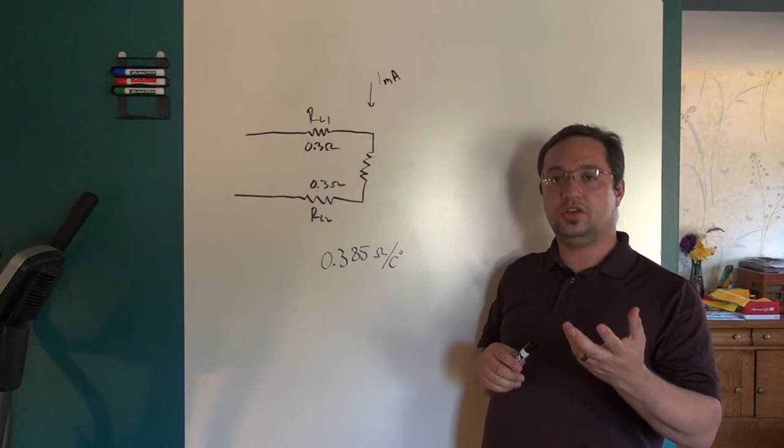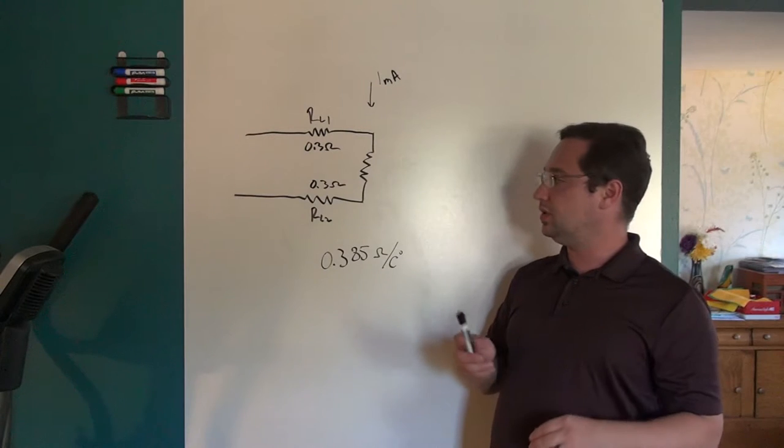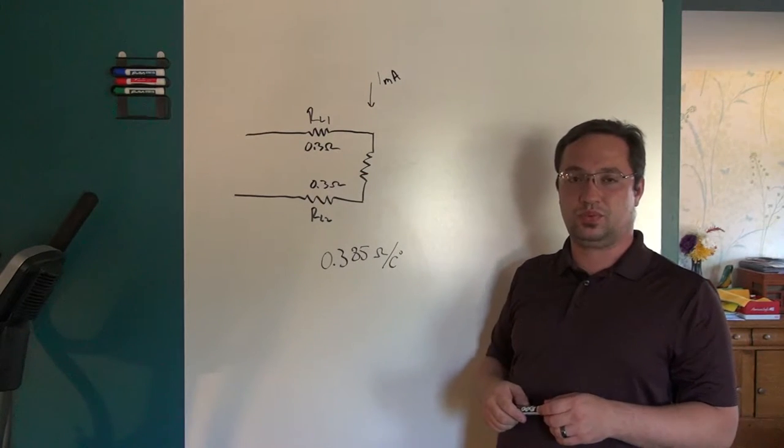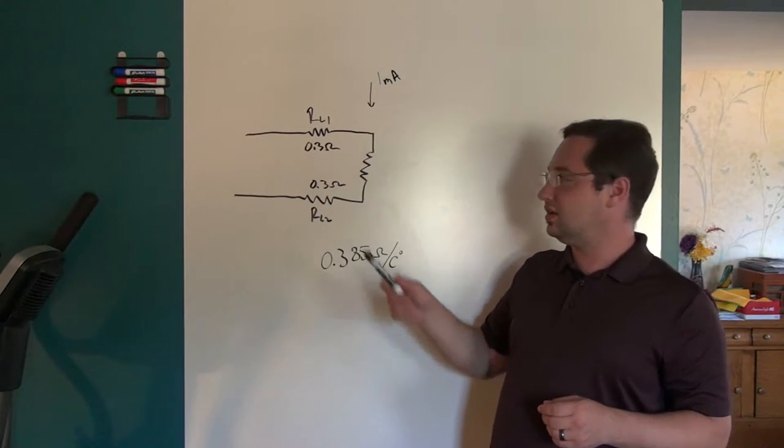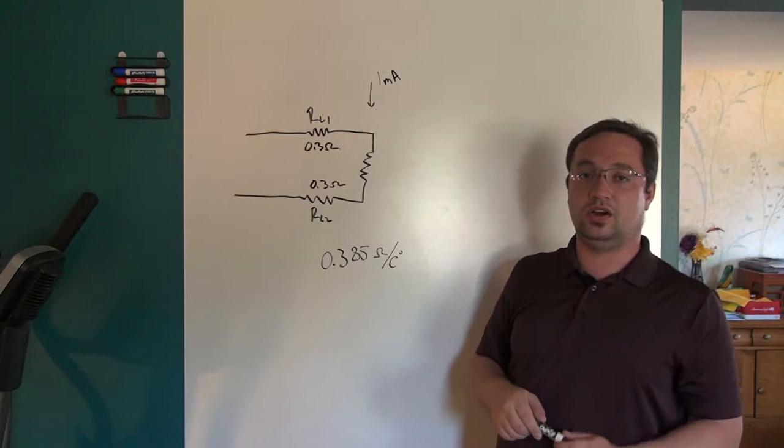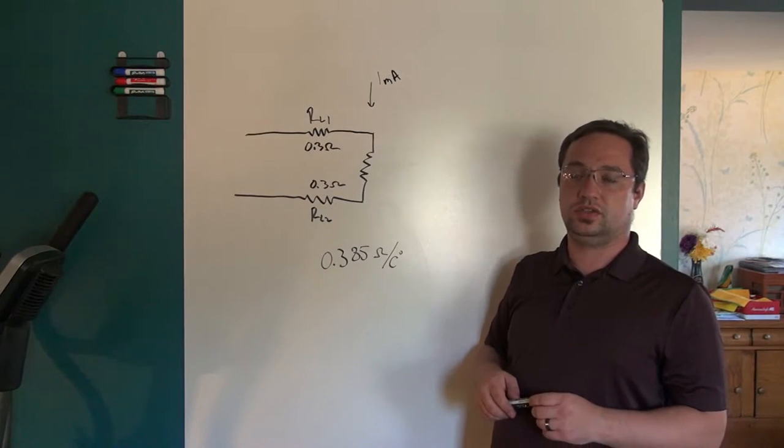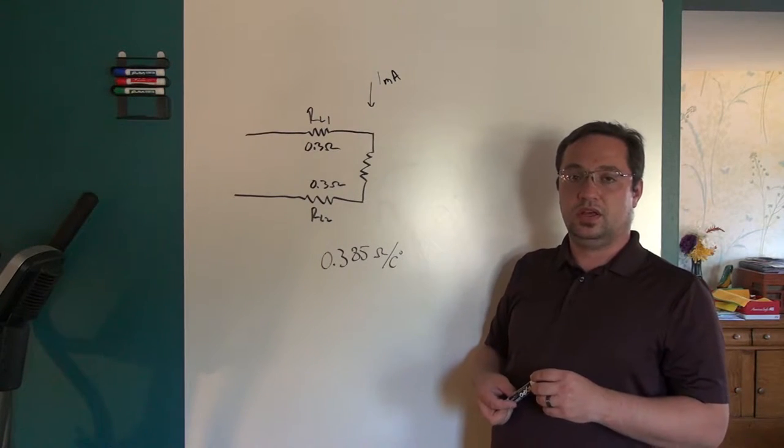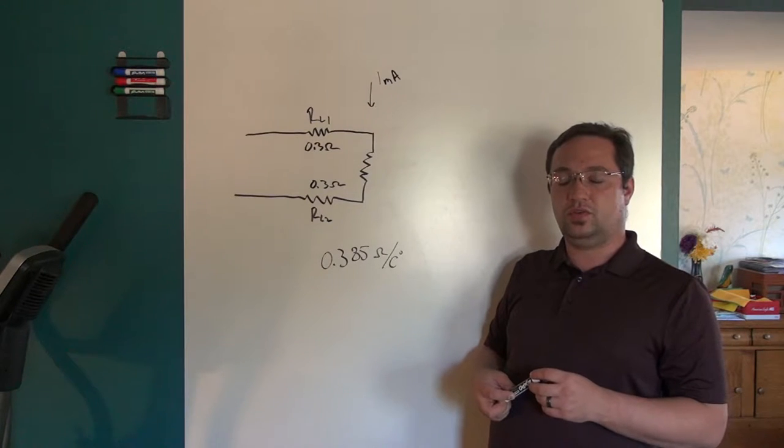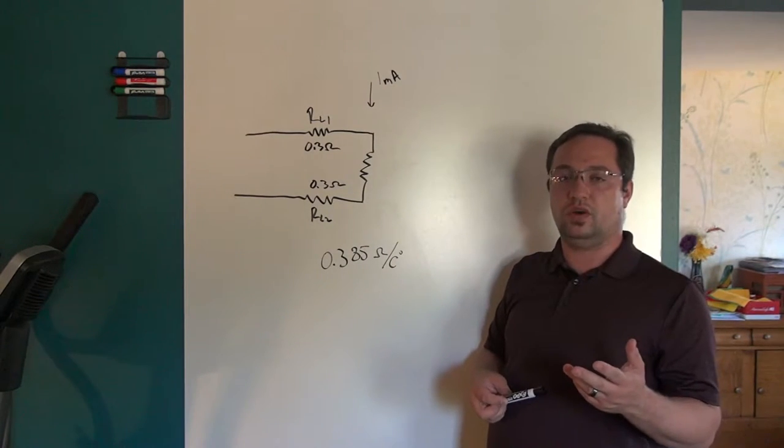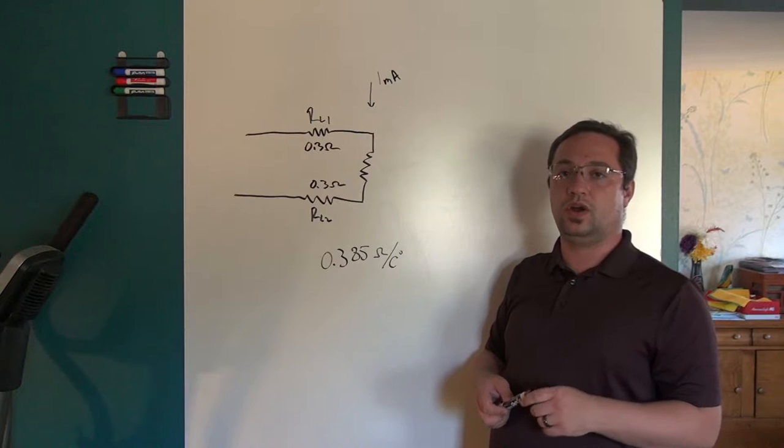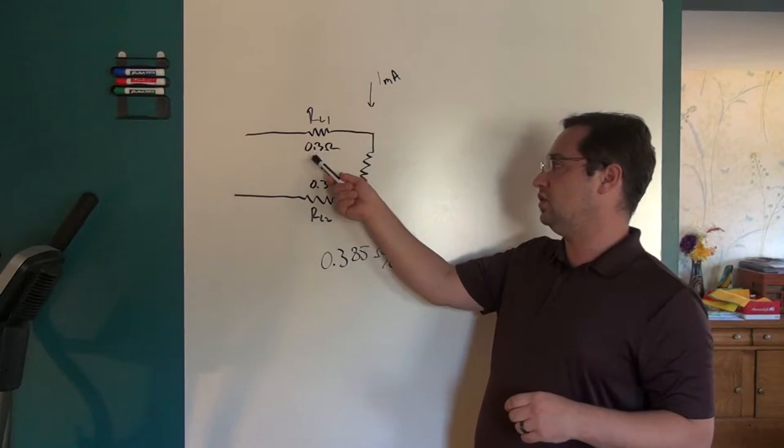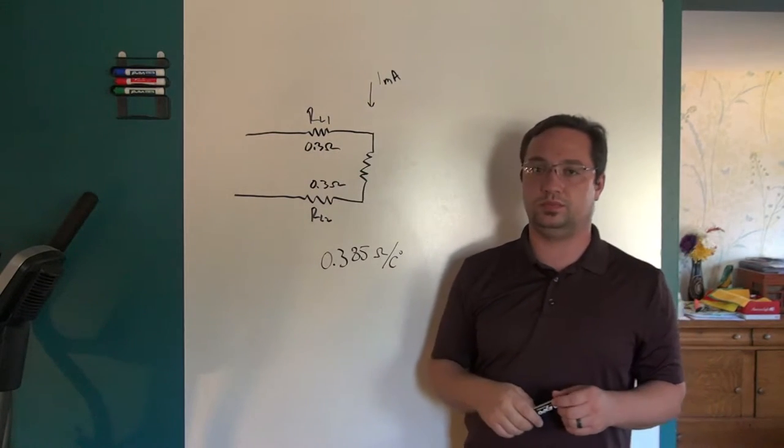The resistive element changes its 0.385 ohms per degree Celsius, roughly. You can take some more decimal places out, and there's actually better formulas to calculate this. But the two resistances of the leads here, 3 tenths of an ohm, 3 tenths of an ohm, combined will give you an error of about 1.6 degrees. And when you're trying to take a really precise measurement, that's a pretty big error that gets induced into that.